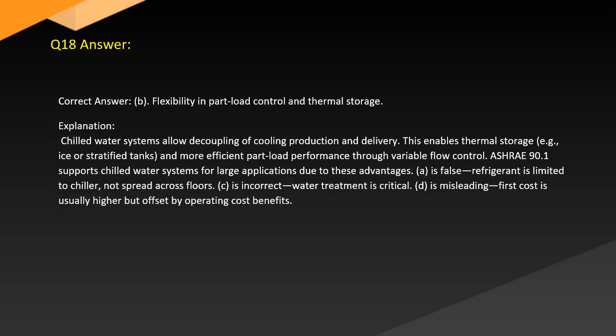Answer. Correct answer B. Flexibility in part load control and thermal storage. Explanation. Chilled water systems allow decoupling of cooling production and delivery. This enables thermal storage, e.g. stratified tanks, and more efficient part load performance through variable flow control. ASHRAE 90.1 supports chilled water systems for large applications due to these advantages. A is false. Refrigerant is limited to the chiller, not spread across floors. C is incorrect. Water treatment is critical. D is misleading. First cost is usually higher but offset by operating cost benefits.